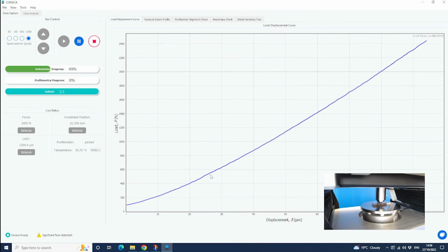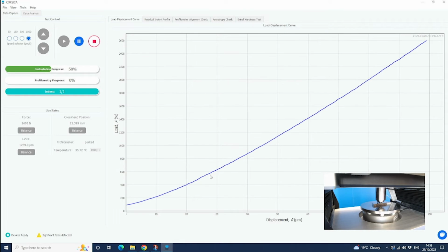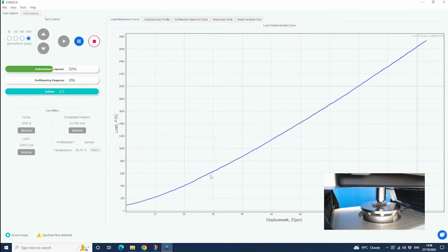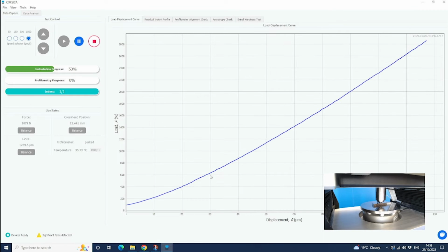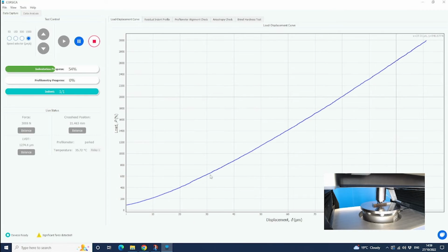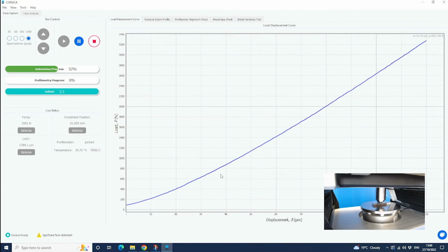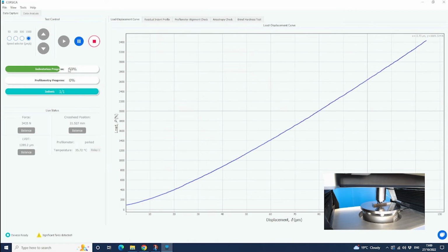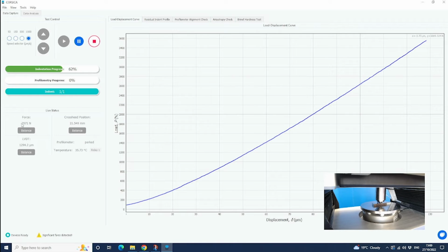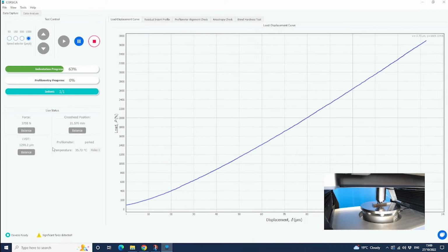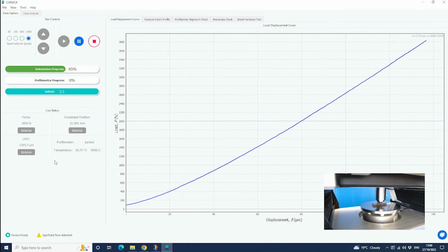If you had a much softer material, the 300M Mar-aging, in its heat treated form is typically quite hard, but if you had a much softer material, we would achieve the same depth with a much lower load, and the software would know to stop at that point. We can see our progress bar building, our live load and LVDT readings are giving a measurement.